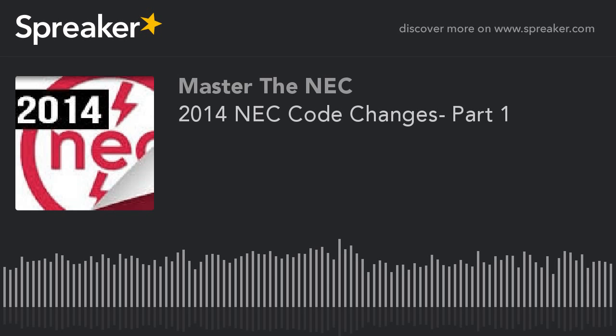Okay, now I can monitor the normal systems in a building. The fire pump's obviously not on in that time. I can manage any of these. The emergency system's not on during that application. I can manage the general use applications of a building. But when you have an alternate power source that is designed to come on during one of these conditions, the last thing you want is to have a power management system that maybe cuts the power down on certain aspects of a building after, say, 9 o'clock at night, and then have an emergency or a fire pump condition. And we all know the requirement for a fire pump is to run until it burns up. Last thing we want is to try to save energy there. So the alternate power sources really can't be controlled by this energy management system.